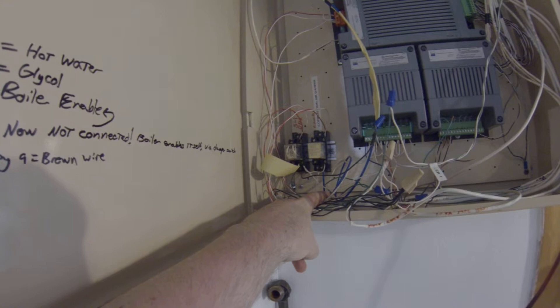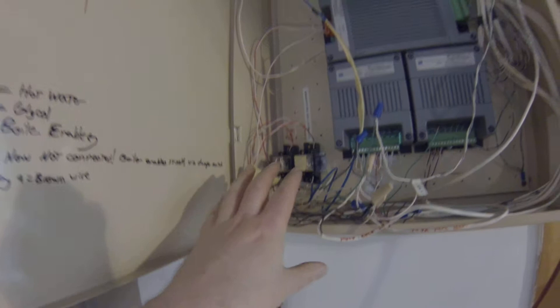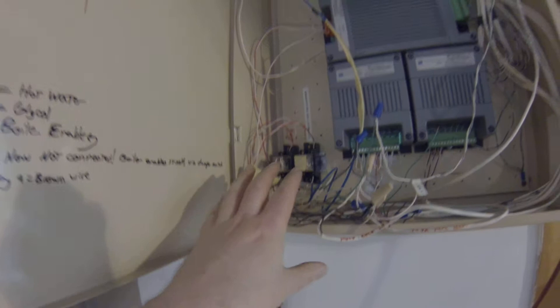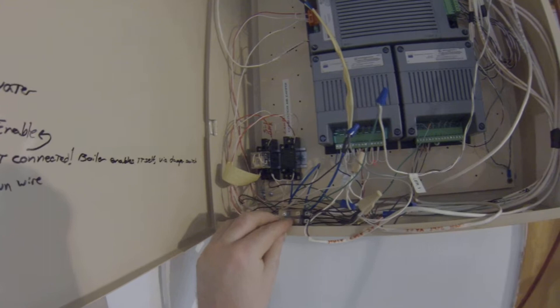So power is always being applied to this damper to open yourself or close yourself. The damper shuts as the motor reaches either end and just sits there. Since we've disabled the main controls, there's never going to be a signal here, so we want to pull this relay. That means the damper is under manual control now.